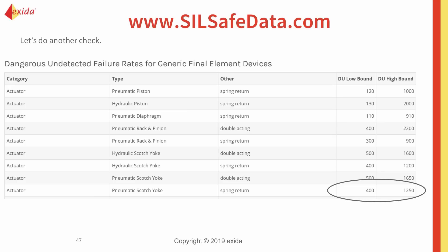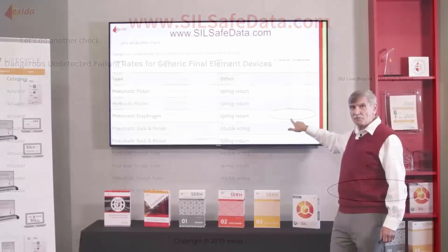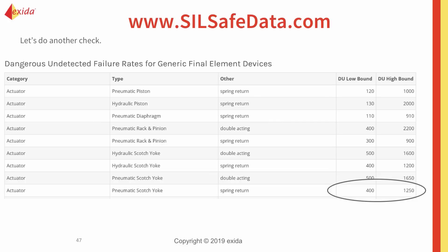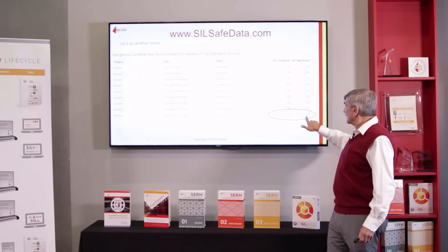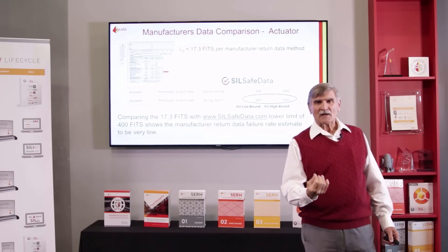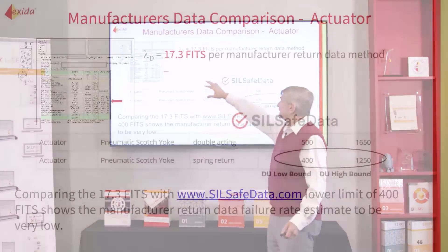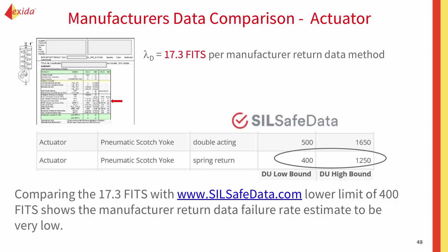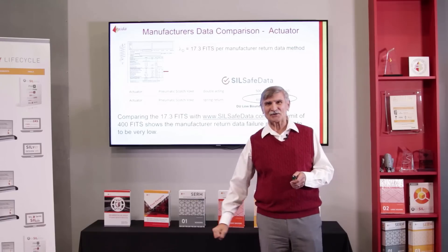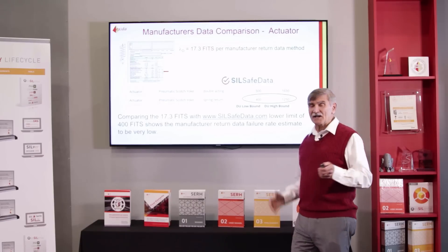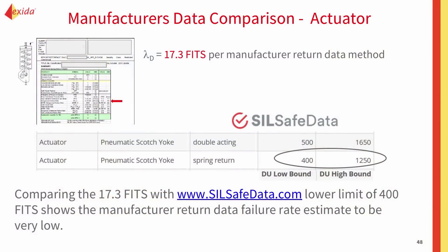Let's focus on a pneumatic scotch yoke spring return. Even with unreasonable limits of plus or minus three sigma, the dangerous undetected failure rate should be a minimum of 400 up to somewhere around 1250. So I get a piece of data — I use SILSAFE data to do a comparison, I pull out the data sheet and it says 17.3 fits. The low limit is 400. This is more than an order of magnitude too low. Quite frankly, this is exactly the sort of thing you get when manufacturer's warranty data is used with optimistic assumptions on the part of the manufacturer. Now you can use SILSAFE data to reject this particular data.